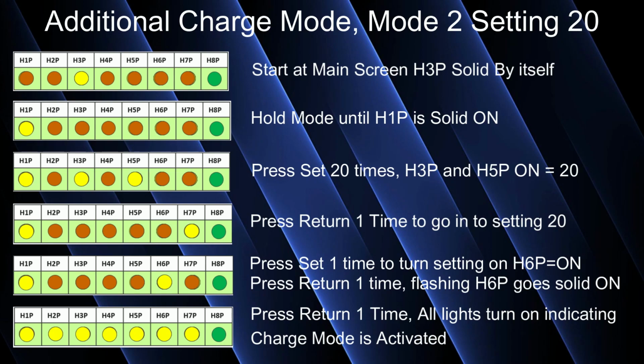And on the older boards, this is how you know that you've enabled the additional refrigerant charge mode. Now at this point, you need to make sure that the bottle of R410A is on the scale. The scale is zeroed out. The hoses are purged, and you've connected your hoses to the refrigerant charging port on VRVS, VRV Life, SkyAir, the hybrid super multi RMXS systems, VRV2, VRV3, all those systems came with a charge port. And usually that charge port is right next to your main service port. So that's where you want to hook up the hose.